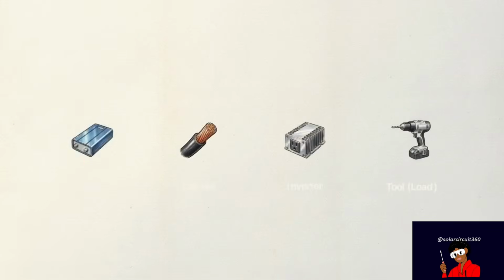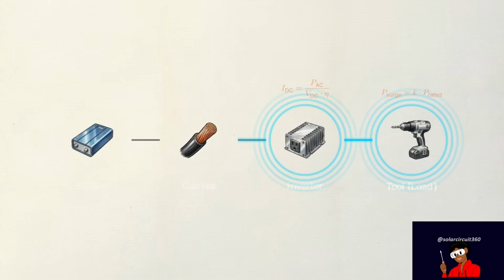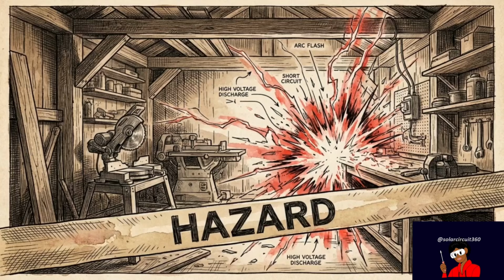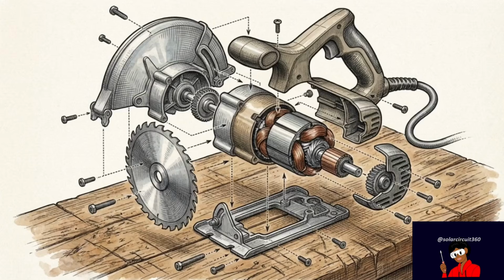To understand why these failures happen, we have to map the exact electrical behavior backward. We will start at the tool, move through the inverter, travel down the cables, and finally analyze the battery itself. Ignoring this complete DC current loop turns a functional off-grid workshop into a severe thermal and electrical hazard. We begin at the end of the line, the power tool itself.